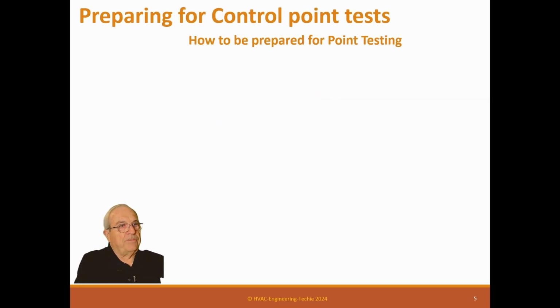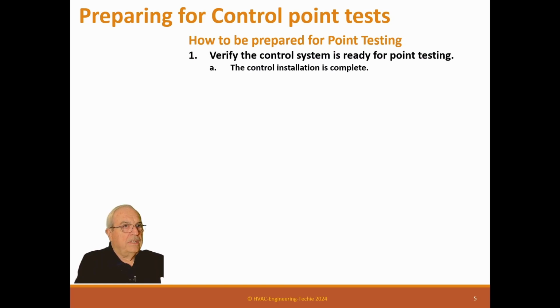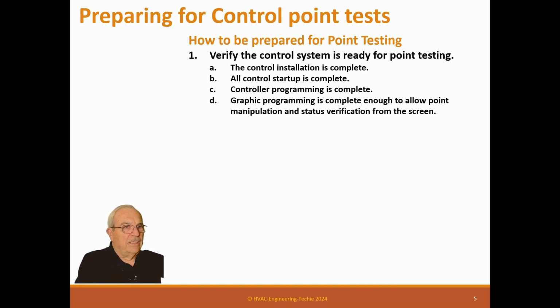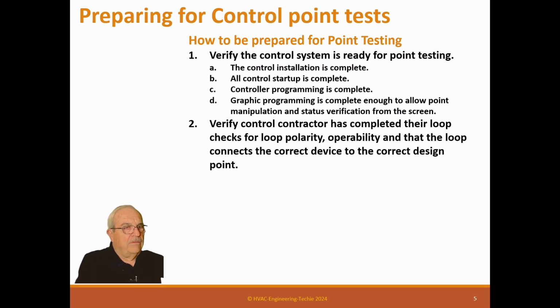All right, preparing for the point test. What do you have to do? How to prepare: verify the control system is ready for point testing. The controller installation is complete. All controller startup is complete. Controller programming is complete. Graphic programming is complete enough to allow point manipulation and status verification from the screen. Verify control contractors have completed their loop checks for loop polarity, operability, and that the loop connects the correct device to the correct design point.